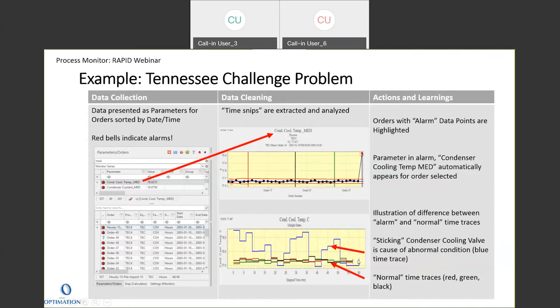This displays that the blue batch had something happening differently, and ultimately it was a condenser valve that was sticking — it was jerky, basically — and that was causing the problem.